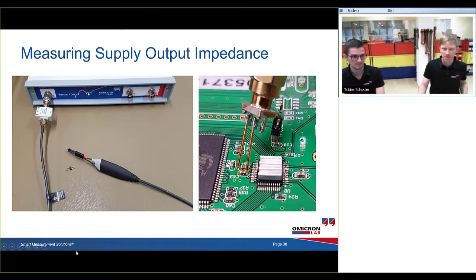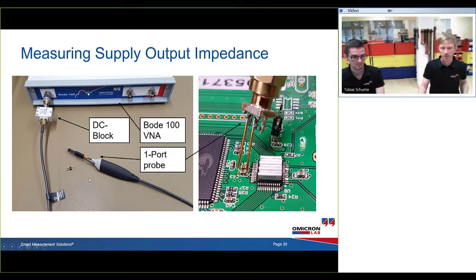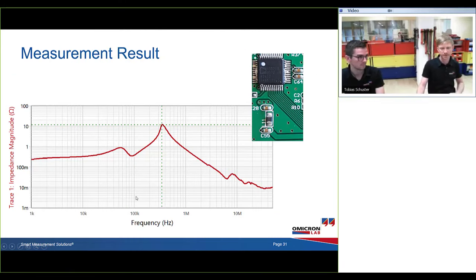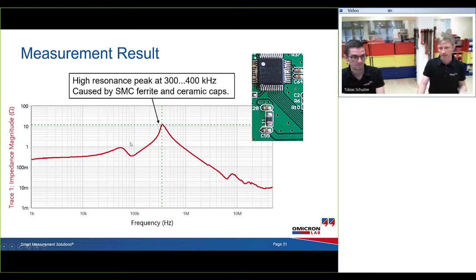We did measure the output impedance using a 1-port probe, connecting very close, directly at the decoupling capacitors of the ADC, and used a DC block to protect the Bode 100 and a 1-port impedance measurement to measure the output impedance. The plot looked like that. From 1 kilohertz to 50 megahertz, the output impedance is not really low. It's about 200 milliohms. And then at 100, 200, 300 and 350 kilohertz, there was a really high peak in the output impedance, around 10 ohms or so. That's mainly caused by resonances between the ferrites and the ceramic caps in the filters.